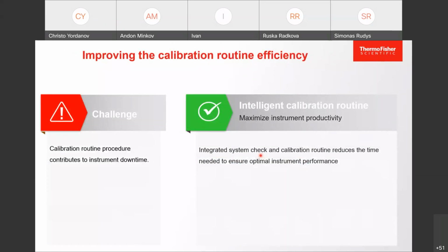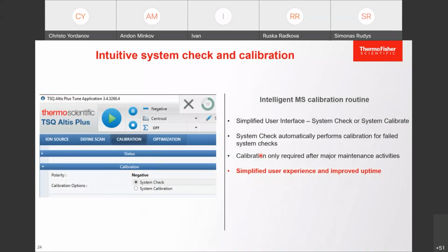Another thing for improved productivity is how much time the instrument is running, what is the uptime and downtime of the instrument. So we can increase uptime by reducing downtime. Downtime can be when the instrument is not performing and when it's not running. And another thing is how much time we are spending on system calibration and checks. So on TSQ Plus, we have implemented system check and system calibration.